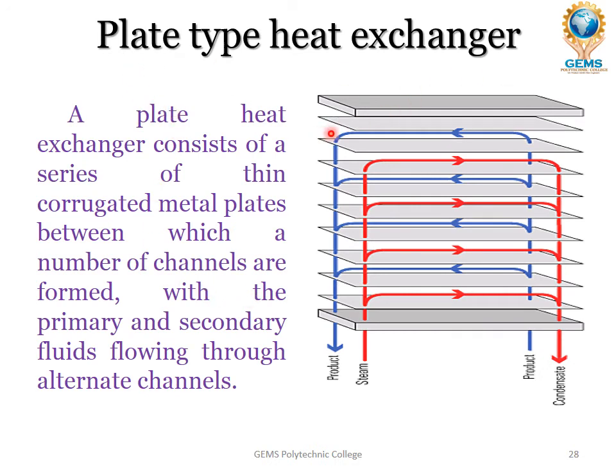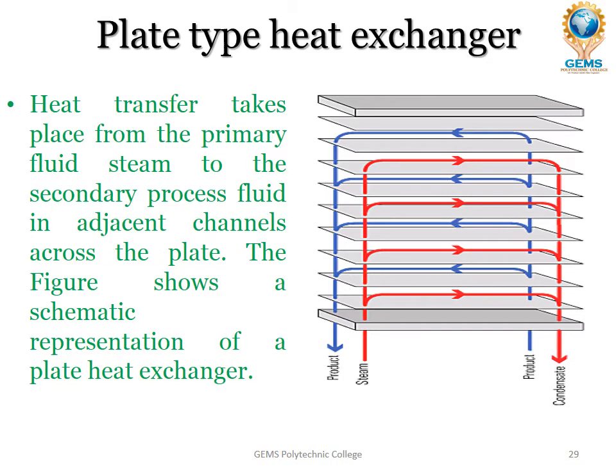So next type is the plate type heat exchangers. A plate type heat exchanger consists of a series of thin corrugated metal plates between which a number of channels are formed with the primary and secondary fluids flowing through alternative channels. So there are a number of thin plates arranged parallelly, and there are channels provided in this plate through which hot and cold fluid, that is the primary and secondary fluids, flow through these alternative channels. Heat transfer takes place from the primary fluid steam to the secondary process fluid in adjacent channels across the plate. The figure shows a schematic representation of the plate heat exchanger. So when the product cold fluid goes inside and the steam goes in this direction, heat gets transferred between these two plates.